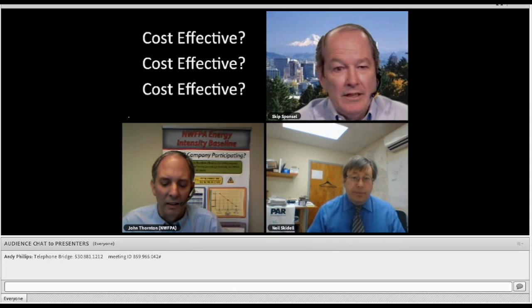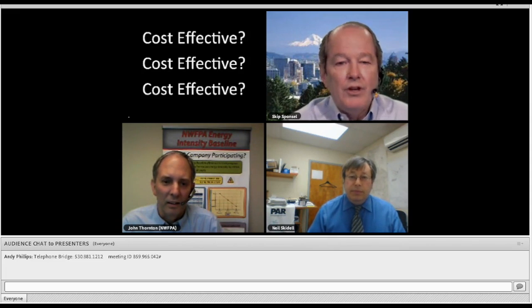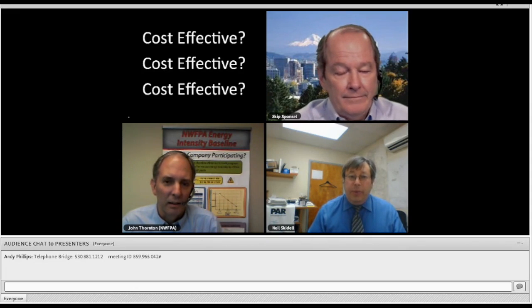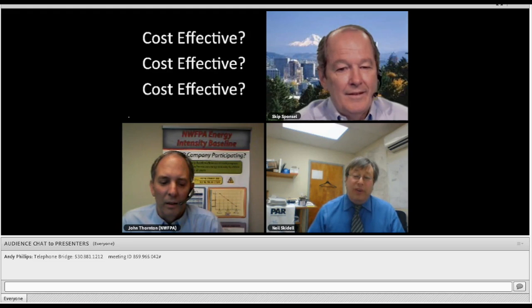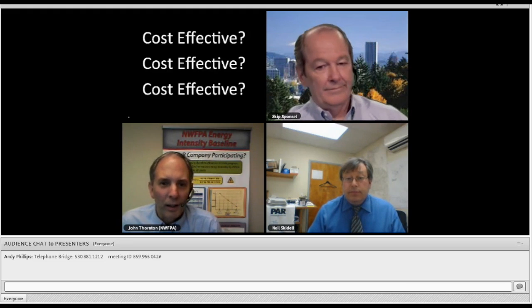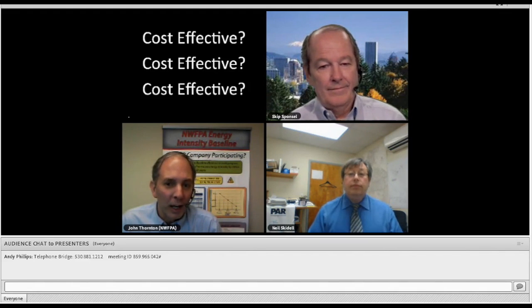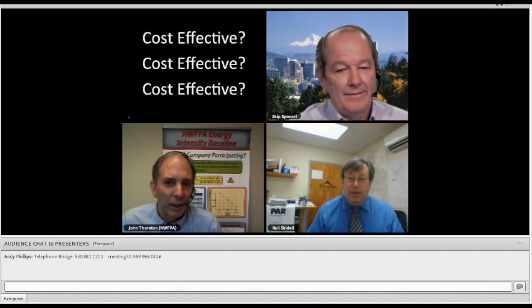Any thoughts before we move to the first presenter on cost-effective issues and what you're looking for it to pencil out? Well, you've got to look at your input cost versus your output product, in this case chilled water or enhanced heat, and then your capital cost to install it and your real estate cost. Some technologies require far more space than others. So you've got installation costs, implications on plant space and real estate, and input cost, which is zero if it's waste heat, though sometimes you need gas or something else. It all needs to be taken into account to get a life cycle cost and see if it reduces your production cost. Location is important too, you want that central plant where your heat source and refrigeration are in one spot, and often there's not a lot of spare space there. The closer you get to that, the lower your capital cost to install will be.